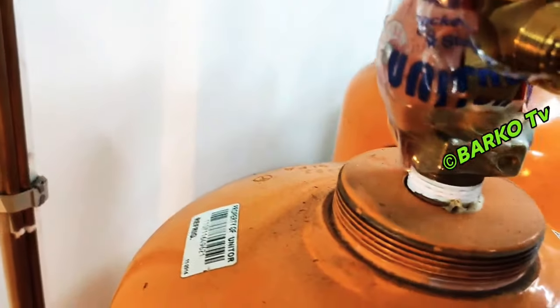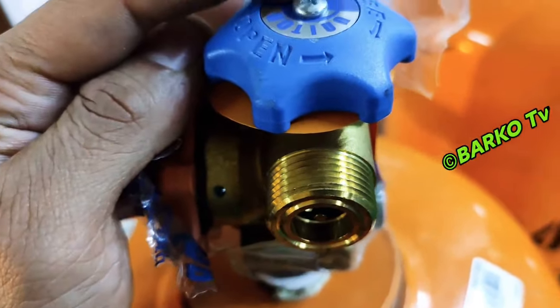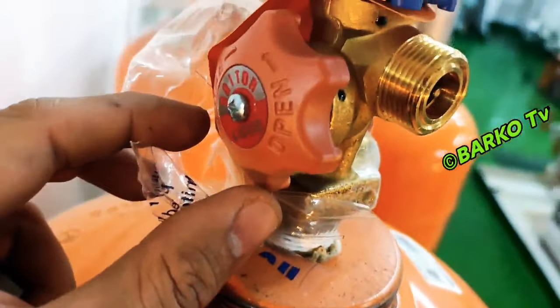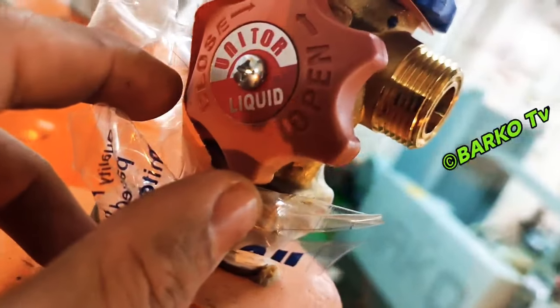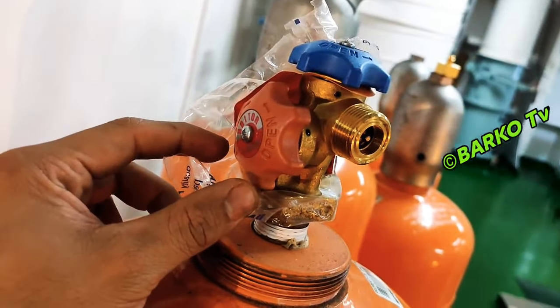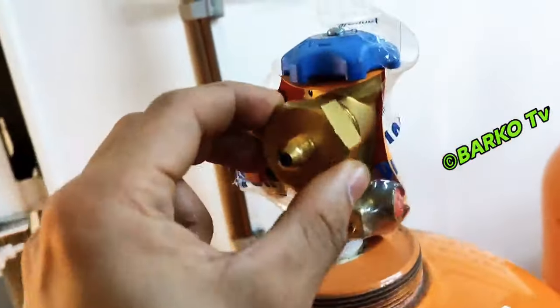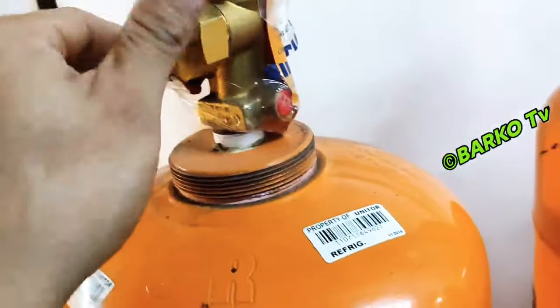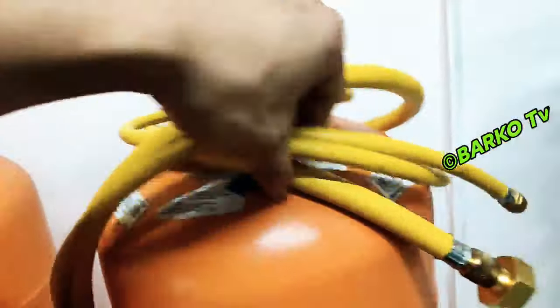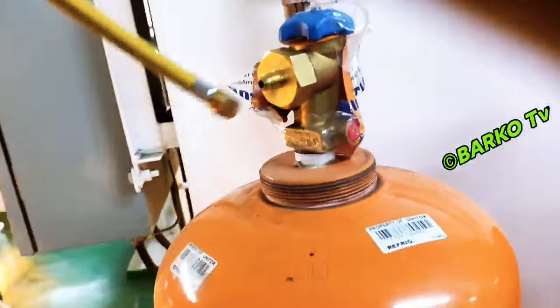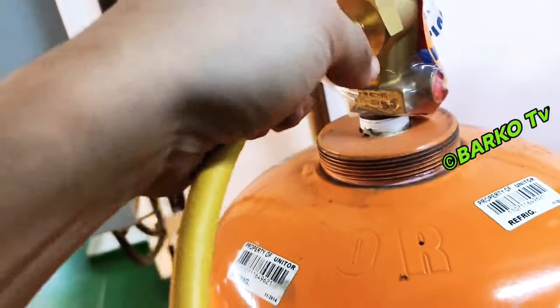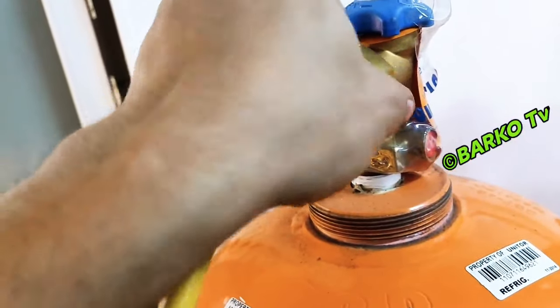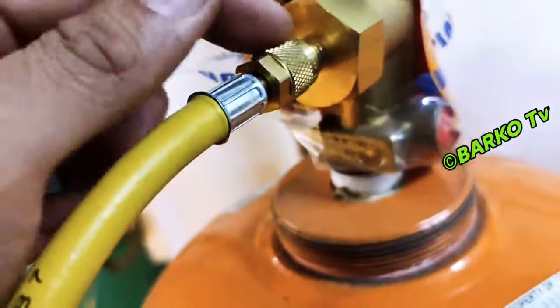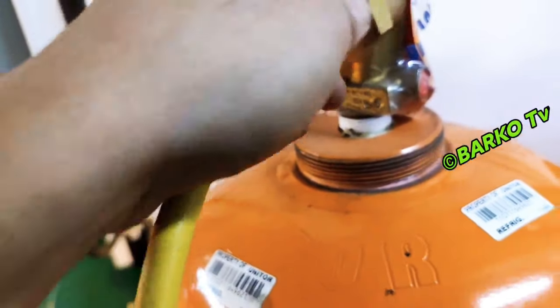This is our refrigerant bottle R404A. This is new, and we need to connect the charging hose. At the top is the gas, at the side is liquid. Okay, first thing to do, connect the charging hose, and then you need to bleed. Open slightly and then bleed so that the air will go out at the charging hose. After we connect, only hand tight.